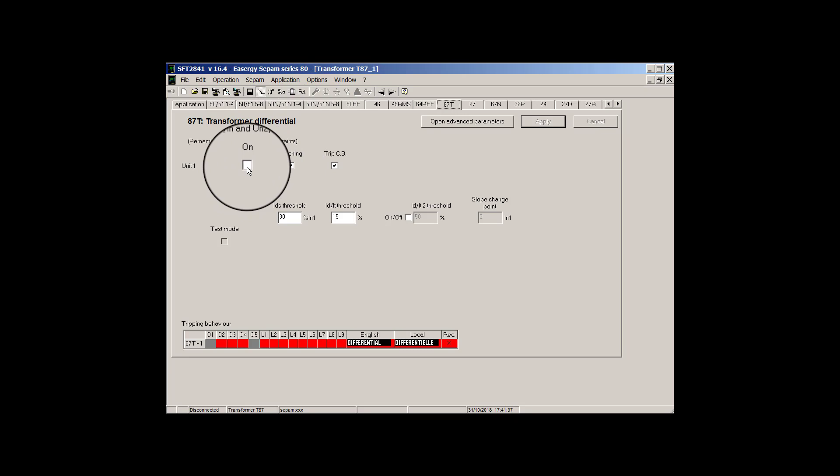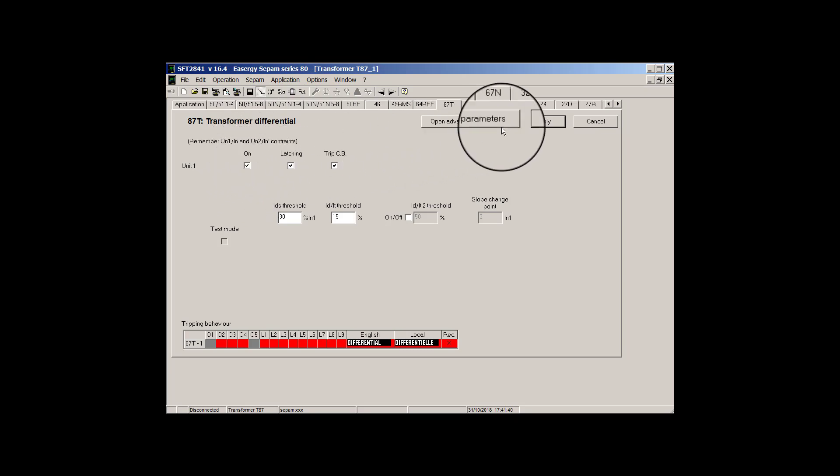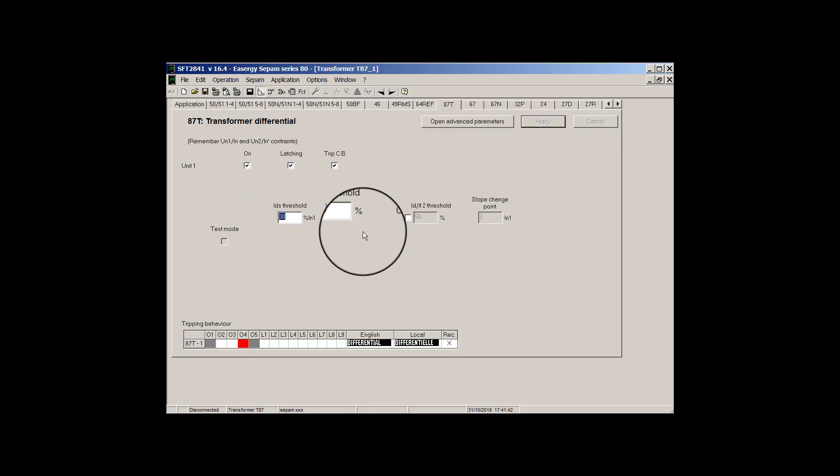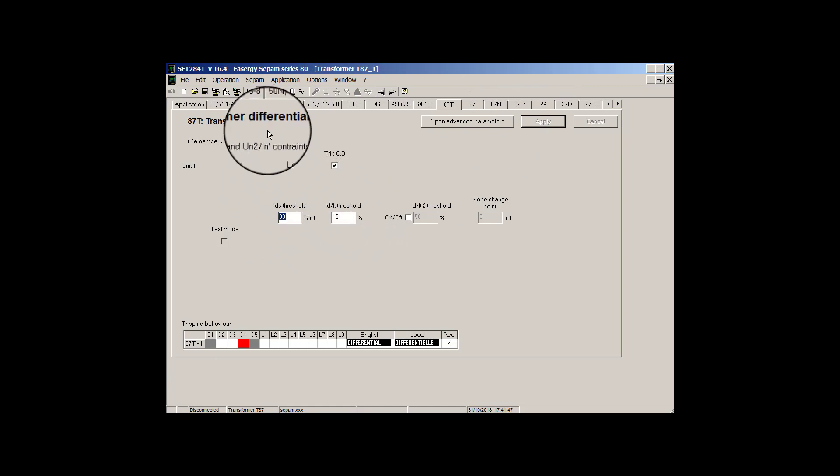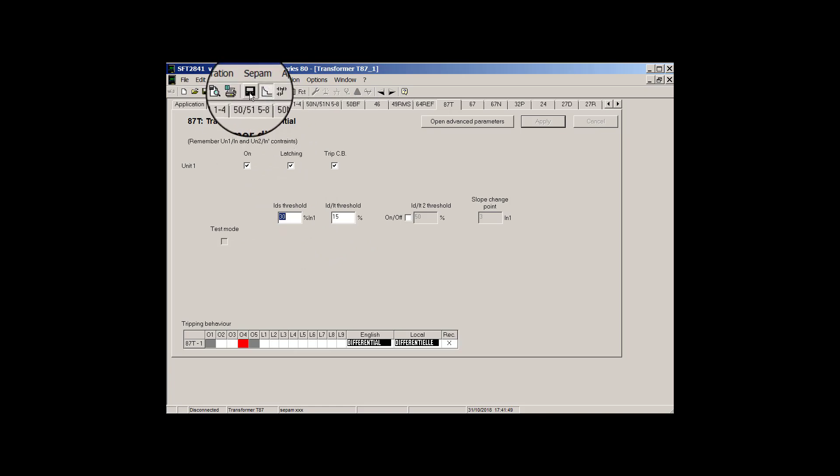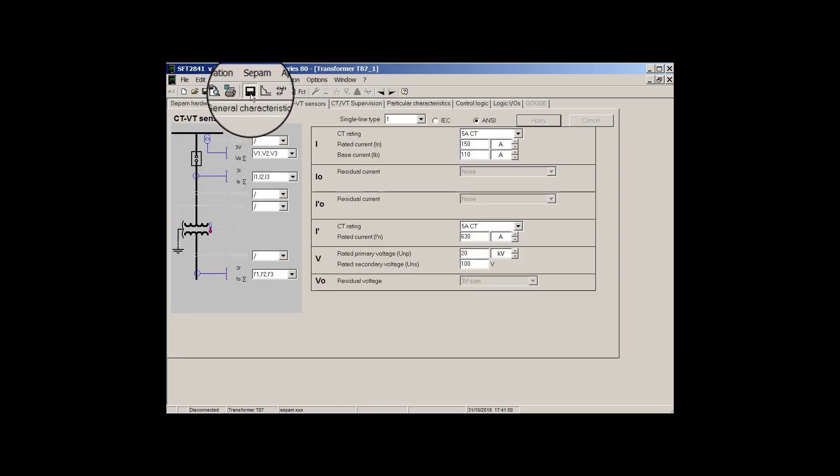The CT, now I just check in protection and I check differential protection. As you see, we are allowed to enable protection because our CT is in range, so the relay accepts to enable transformer differential protection and we can set whatever we want.